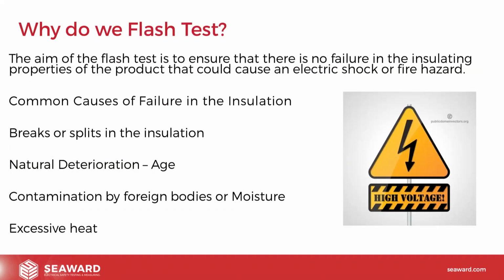So why do we flash test? Well, ultimately we flash test to ensure customer safety when renting out our tools to our end users. The ultimate aim of the flash test is to ensure there's no failure in the insulating properties of the product. So we're performing the test to stress the insulation to ensure that there's no breakdown with the insulation that could ultimately then be the cause of either an electric shock or a potential fire hazard if left running.